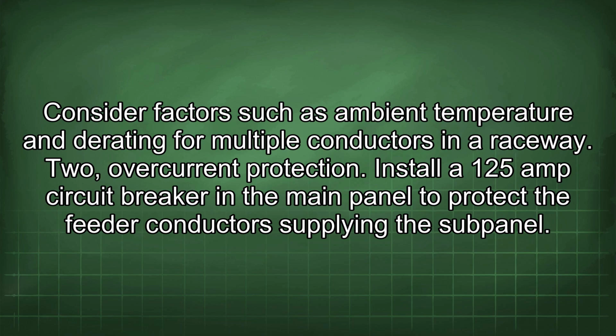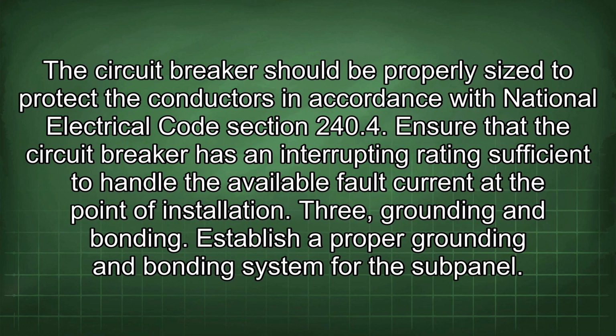2. Overcurrent protection. Install a 125 amp circuit breaker in the main panel to protect the feeder conductors supplying the subpanel. The circuit breaker should be properly sized to protect the conductors in accordance with National Electrical Code Section 240.4. Ensure that the circuit breaker has an interrupting rating sufficient to handle the available fault current at the point of installation.